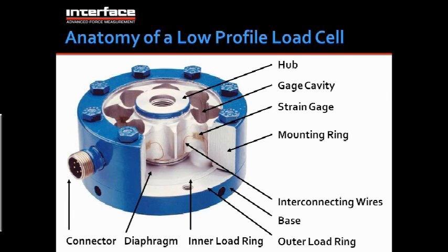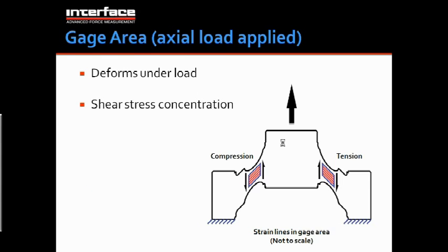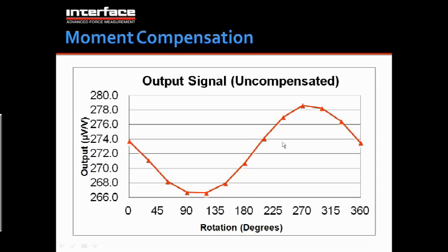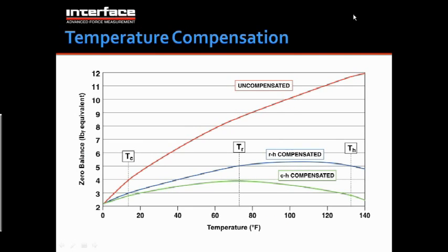I'll take that one, Nikki, and for that I'll refer back to our diagram here, or the chart. This one here. As the temperature around the load cell is changing, the temperature coefficient of resistance of the metals involved in the fabrication of the load cell, the flexure and the strain gauges, their TCR is changing, and therefore we have an output signal that is changing as the temperature around the load cell is changing.